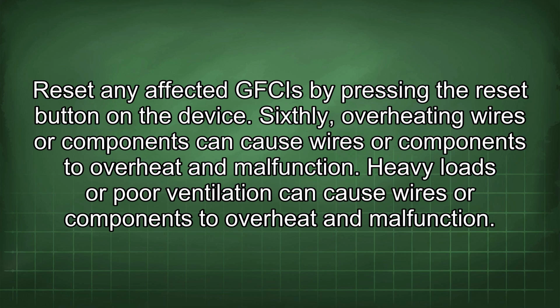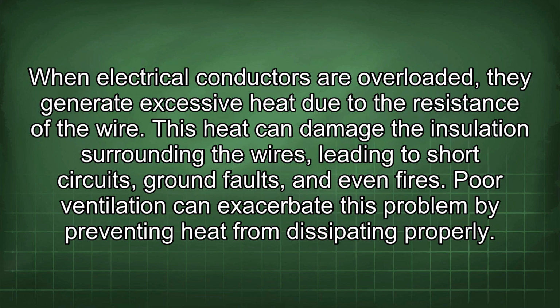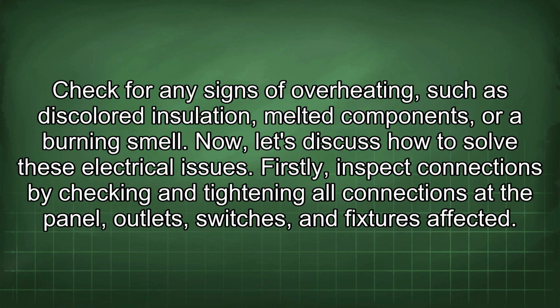Sixthly, overheating wires or components can cause wires or components to overheat and malfunction. Heavy loads or poor ventilation can cause wires or components to overheat and malfunction. When electrical conductors are overloaded, they generate excessive heat due to the resistance of the wire. This heat can damage the insulation surrounding the wires, leading to short circuits, ground faults, and even fires. Poor ventilation can exacerbate this problem by preventing heat from dissipating properly. Check for any signs of overheating, such as discolored insulation, melted components, or a burning smell.